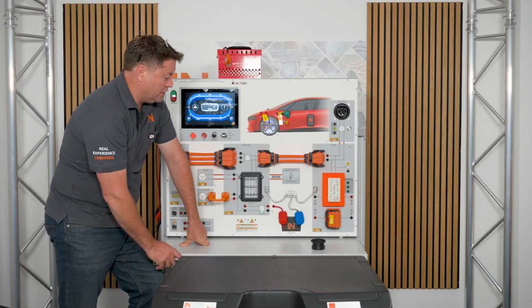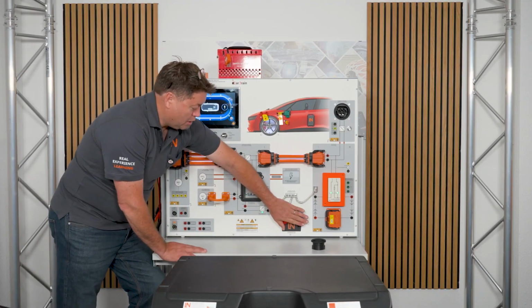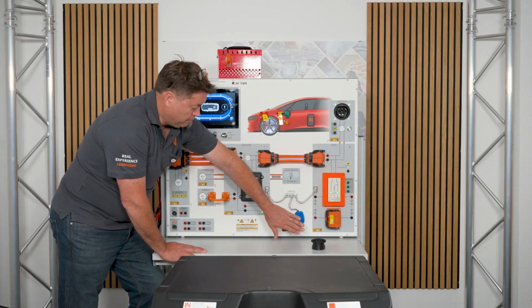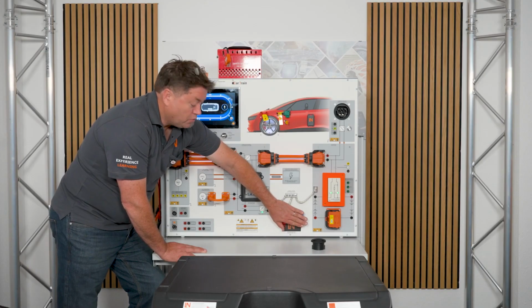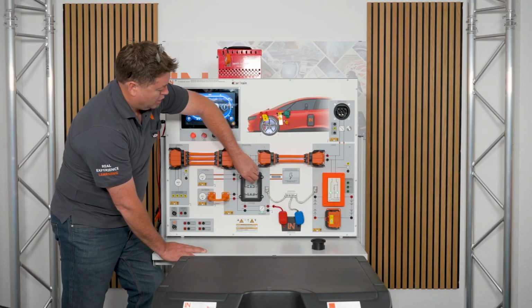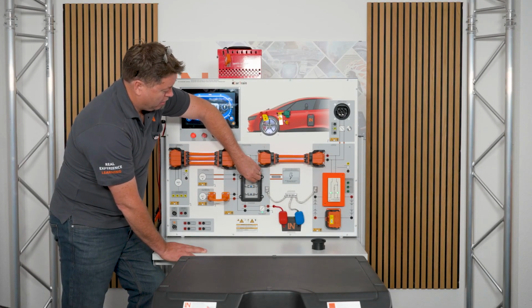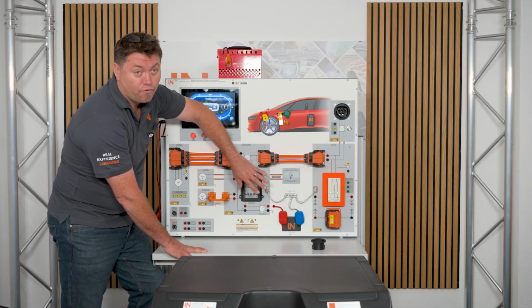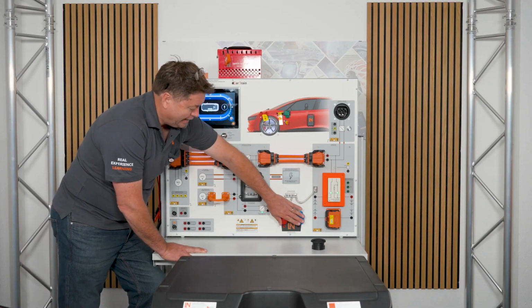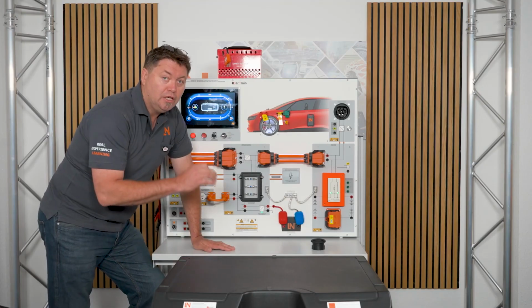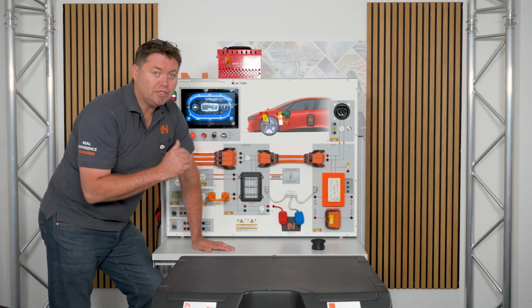So live dead live testing is where you're measuring, for example, on our 12 volt battery down here. So to check that our multimeter is working correctly, come up here to measure our high voltage system to make sure it's free of voltage at 0 volts. And then you go back down to your 12 volt battery again to make sure that your meter is still working.